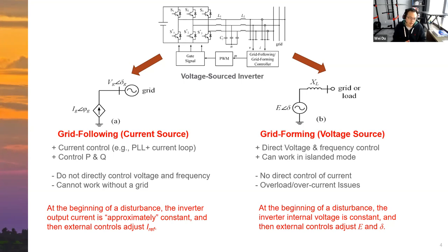People did that from the very beginning, but now I think this kind of control design was short-sighted, because if in the future we really have massive integration of renewables into the grid, grid following control will not work very well. In contrast, the right side is the grid forming concept. Grid forming makes the voltage source inverter approximately behave as a voltage source. The controller directly controls the voltage magnitude and phase angle of this voltage source. This concept mainly came from microgrids, but nowadays people are more interested in studying how grid forming inverters impact the bulk power system.